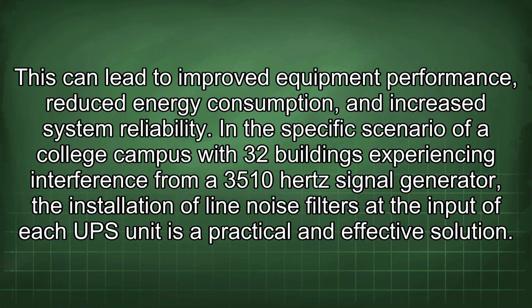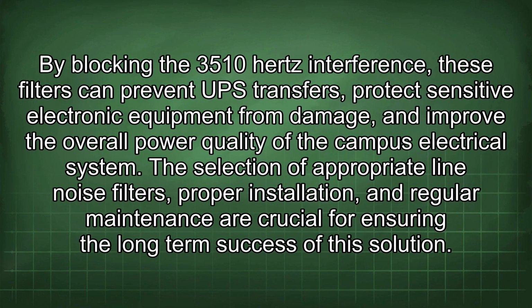In the specific scenario of a college campus with 32 buildings experiencing interference from a 3510 Hz signal generator, the installation of line noise filters at the input of each UPS unit is a practical and effective solution. By blocking the 3510 Hz interference, these filters can prevent UPS transfers, protect sensitive electronic equipment from damage, and improve the overall power quality of the campus electrical system.